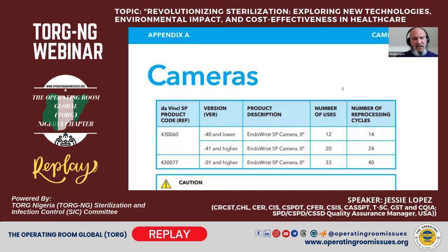Well, there are many times where an individual is going to be scheduled for surgery, and as technicians, we pick the cases and we have the device ready to be used on that patient. It's been sterilized and it's ready. The patient gets into the room, and upon speaking to the patient or something goes wrong in the case, we have to cancel that case. We do not utilize the product, but the product is now considered contaminated because we opened it. So it has to go back to the department to undergo the process all over again. That counts as a reprocessing cycle. So you have just wasted a life of that device. Usage is usage. I used it 12 times on a patient.